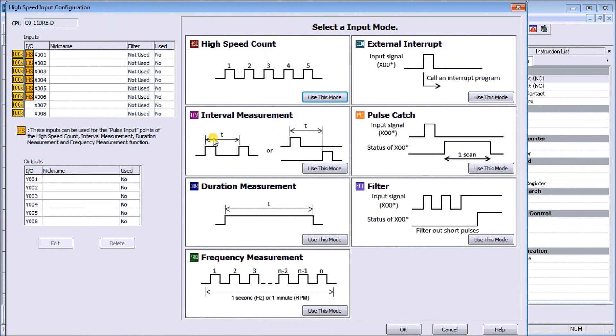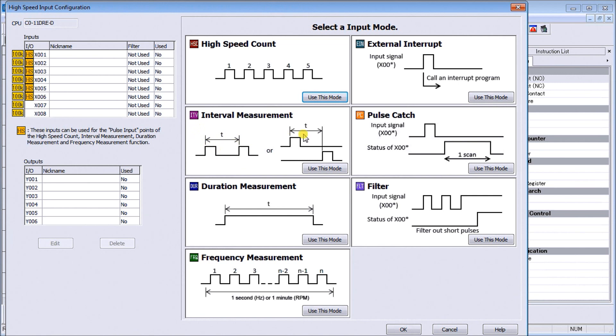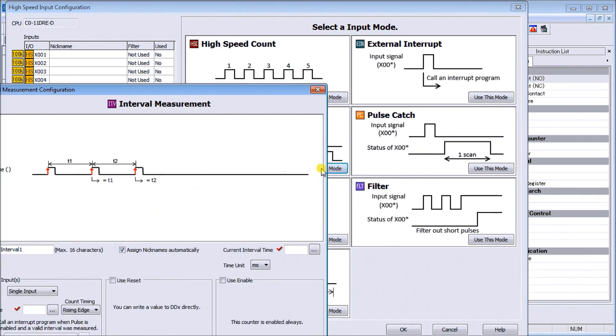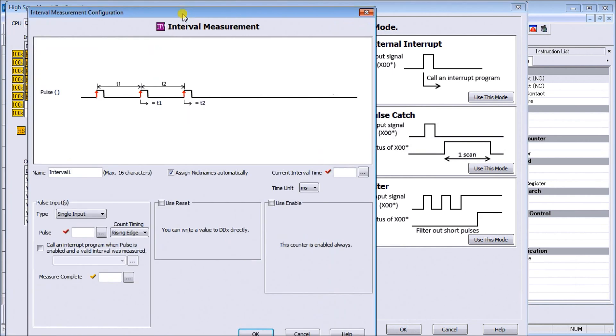What we're looking for is interval measurement, which is right here. Through our timing chart, we can measure the starting of each pulse and time that interval, or we can use dual start and look at the beginning of the first one versus the beginning of the next one. We'll hit 'use this mode,' and our interval measurement configuration comes up.